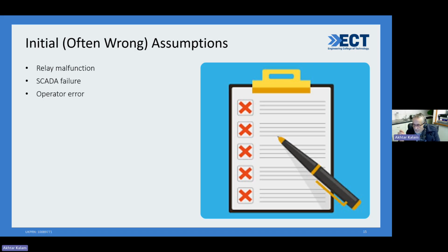So the answer to your question is that all the assumptions you had were incorrect. So do not jump to conclusions, my friend, because you will never know the true cause if you jump to the conclusion. And for God's sake, take responsibility, because you have that urgent desire to blame the instrument immediately. You say, oh, protection was the problem. SCADA was a problem. Operator was a problem, right? Don't make that mistake. Don't come to a conclusion too early. Try and find out what really happened.